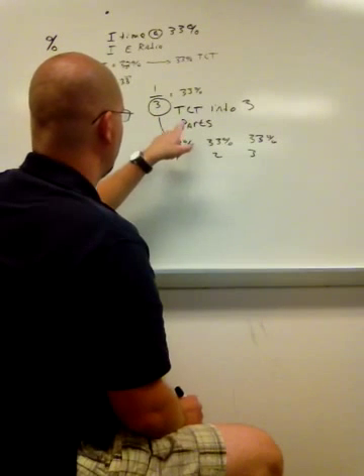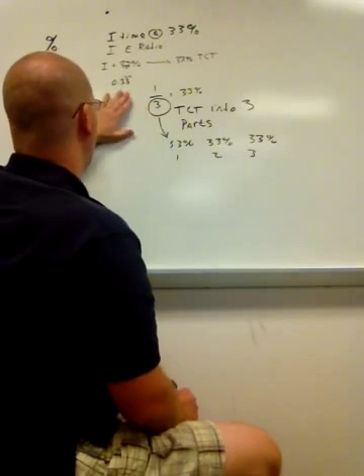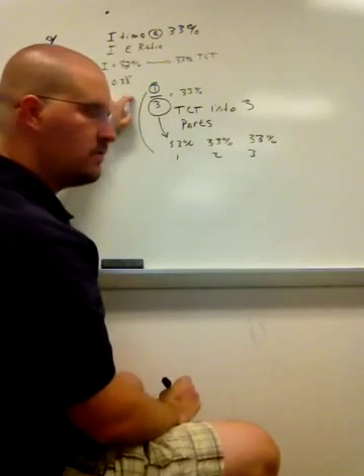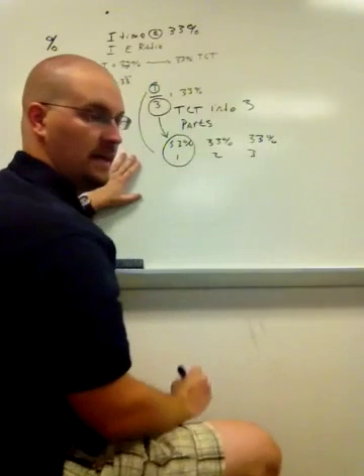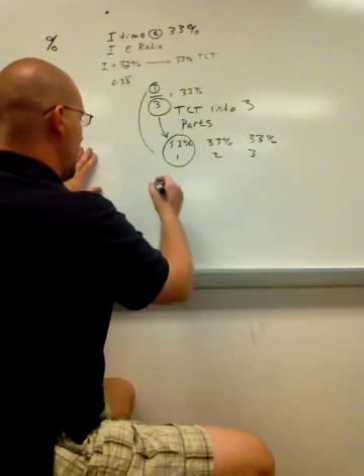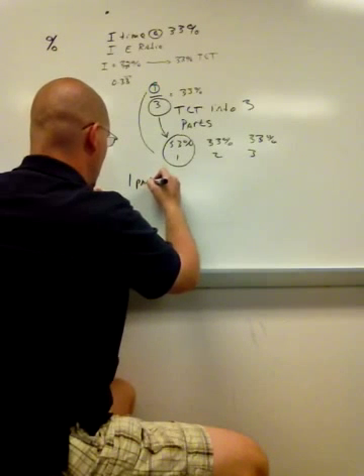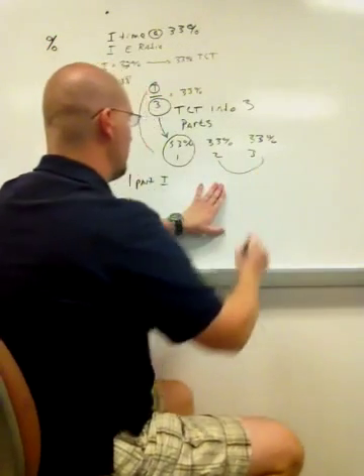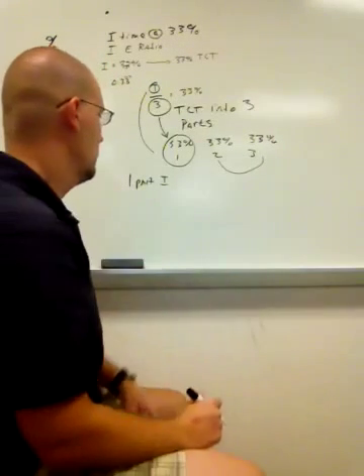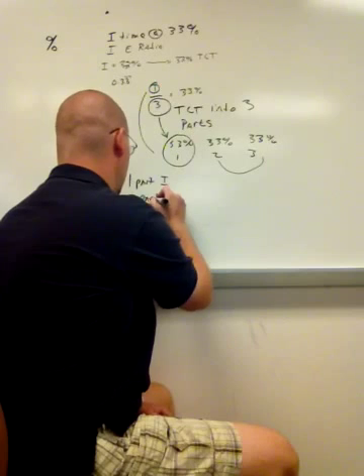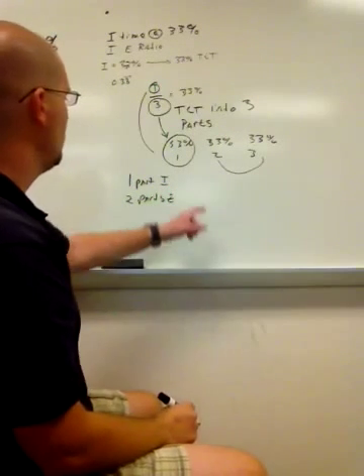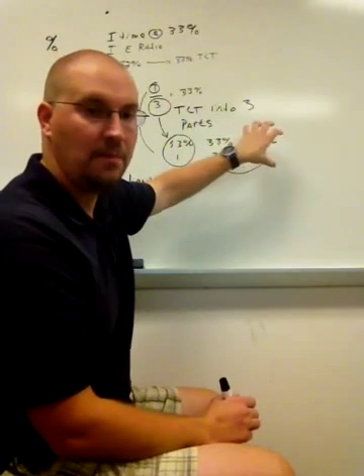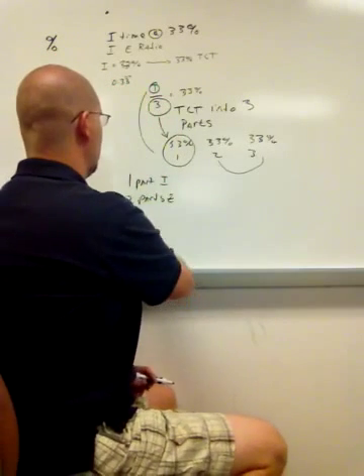And then I go, my total cycle time is broken into 3 parts. 1 part must be my I time. So I'm going to take one of these 33% and make that my I time. So 1 part I, and what do I have left over? I have these other two 33s left over. So 2 parts E. So my I to E ratio is 1, there's my 1/3, to 2, whatever's left over for my E part. Hopefully that makes a little more intuitive sense.